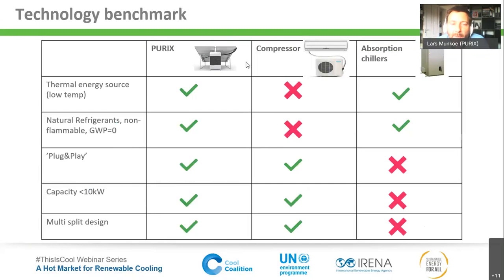So what we decided here was to make use of two conventional technologies. Solar thermal has been on the market for decades, well-proven, reliable. Absorption chillers, a technology invented in the 1850s, can produce cold or cooling from a heat source instead of electricity, no moving parts, no compressor, very simple, long technical lifetime. Unfortunately, they are not available as a complete cooling system. You can easily buy an absorption chiller from 100 kilowatts to 1 megawatt to 200 megawatts, but that doesn't give you a cooling system. You need distribution, you need the heat source, you need the automation to make it all work together, which is complicated and costly.